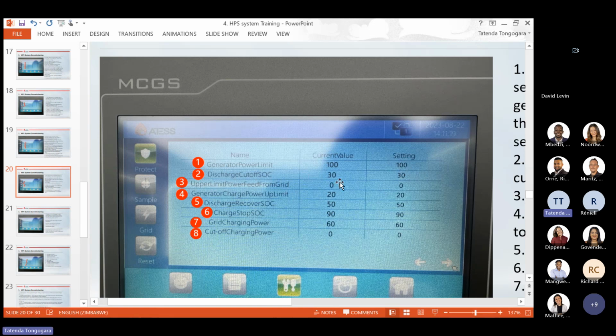And then we have discharge cutoff SOC. So when you're on grid, grid is available, your system will stop discharging the battery at this SOC percentage, like 30%, and start supplying the load with grid. In the event that you lose grid, the HPS will start discharging the battery from 30 till it gets to the under voltage value. So for this one, you can set it slightly higher if you're experiencing a lot of load shedding.